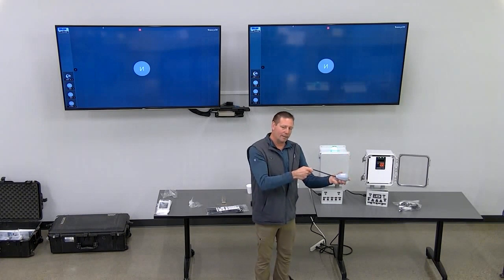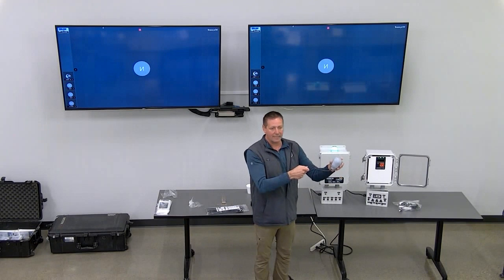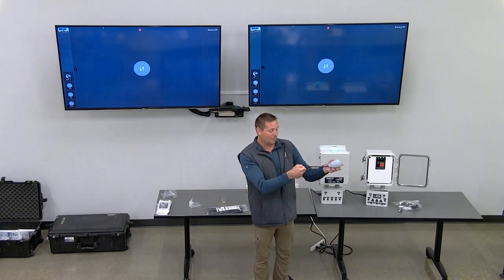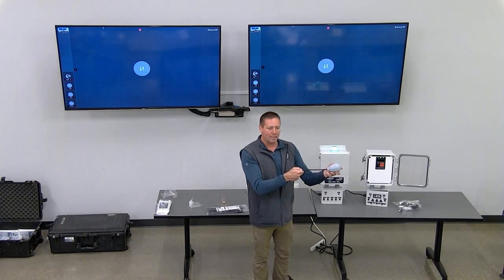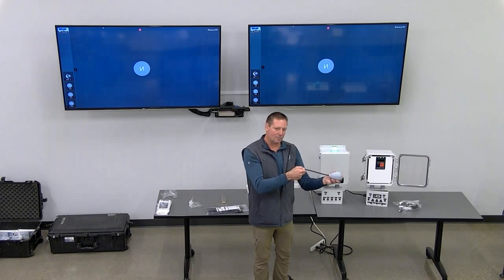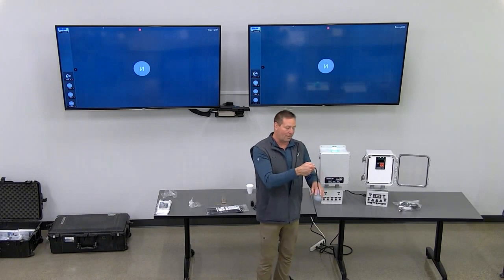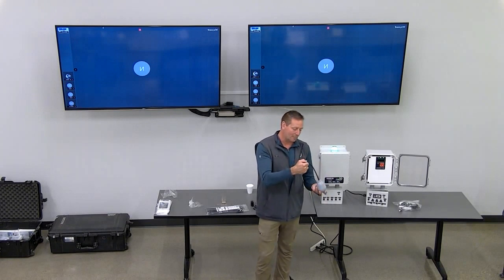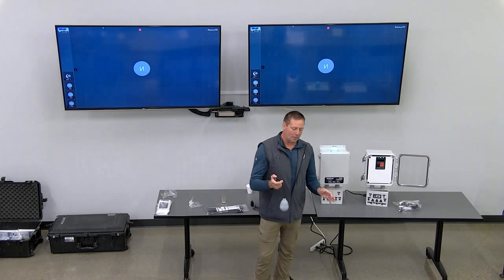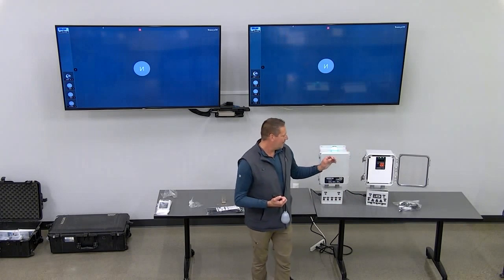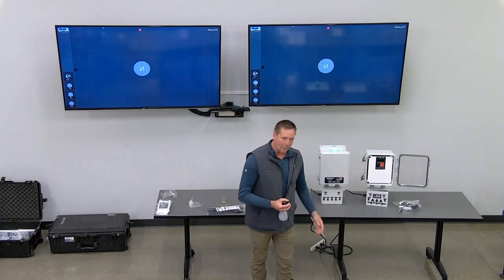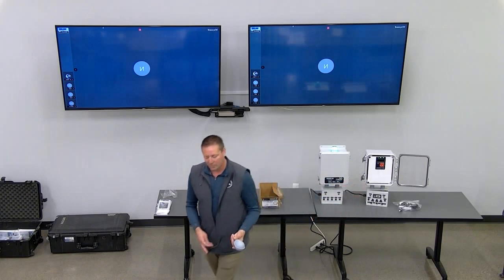And then it pumps liquid down, and then once that time has elapsed, if the pump float is still in the closed position, the contacts are still closed and current is still flowing through there, the pump's still not going to run because it's now going to go back into that rest period of 4 hours. And now once your 4 hours has elapsed, it continues pumping down. And typically on a time dose system, when the control float drops down and opens that circuit where no power can flow through it, the pump would shut off. However, with some of the digital time dose features, you can actually run out that entire time if you choose. So, hope that wasn't too complicated.